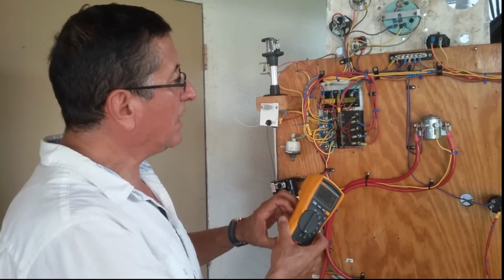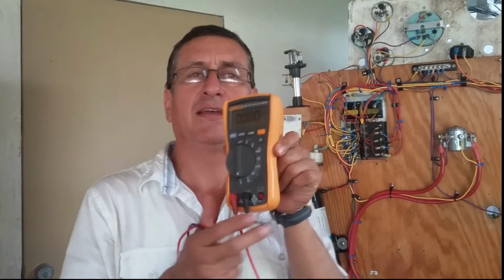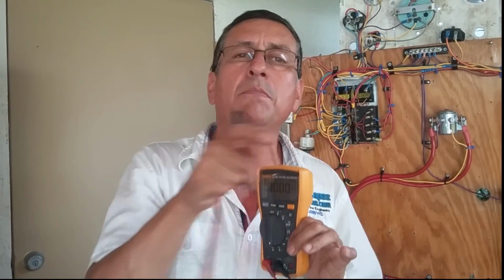I am going to insert my ammeter in series. What is the recommendation? I have the positive wire. I interrupt the wire and I insert the terminals of my ammeter in series between those separated cables. Oh, but I don't like that because I need to cut the positive wire all the time. You don't need to, because you have breakers. When the breaker is off, the cable is interrupted and you can insert the ammeter there. I am going to do that right now.